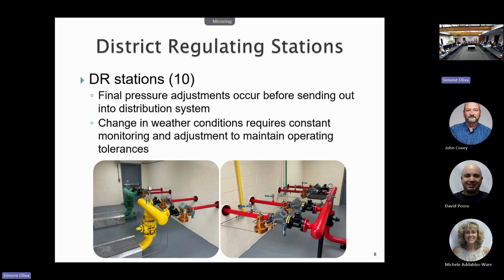The other portion is if we have a really cold night and then a really warm day. All this gas is flowing through our pipeline, then it warms up, but that gas is already going into the system. You lift off the throttle and we get what's called line pack, pressure starts to build because we're not using enough at the end, not putting enough through the cash registers and into people's houses. So we start to see line pack. It's very important that we don't overpressurize, we have MAOPs, so we want to react to those just as quickly. That may just be a turn down of one of these regulators to keep the system balanced.